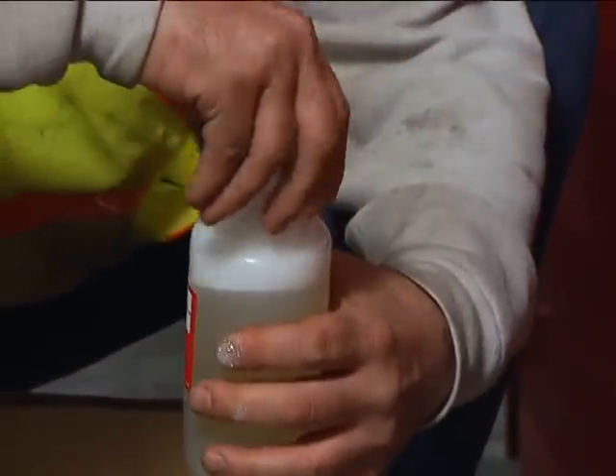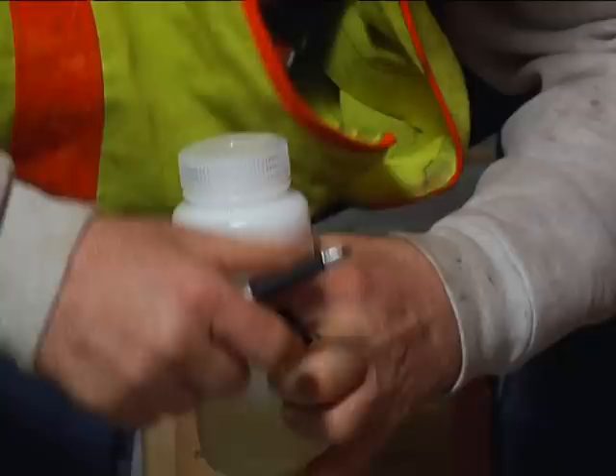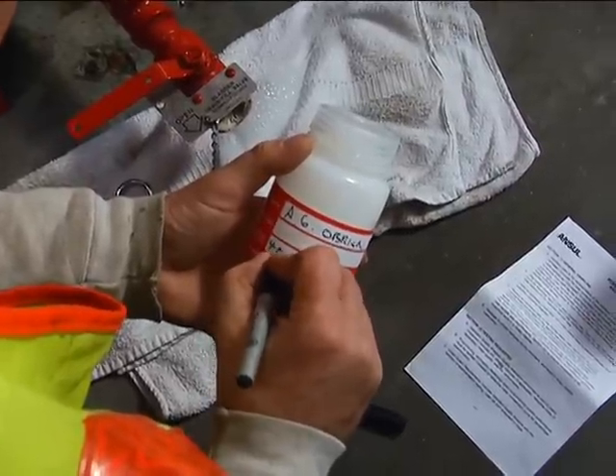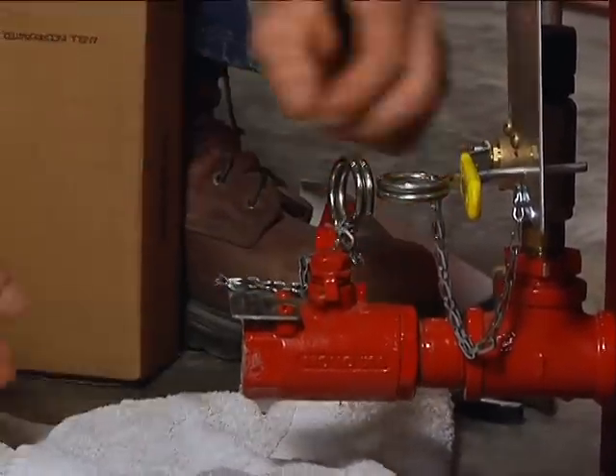Using your ANSUL test kit, collect a small sample of foam concentrate from the bladder tank by completing the following steps. Open the bladder drain fill valve and discharge a small quantity of concentrate — approximately one pint (0.5 liter) — into a clean container. Then close the valve.